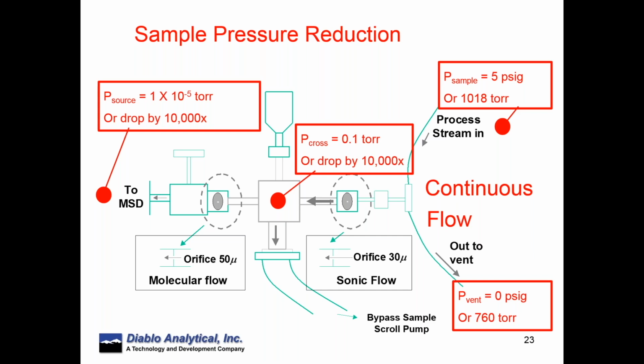And you can see that in the cross on the top, that device is a capacitance manometer that's doing a very accurate measurement of the pressure. And we're going to use that to compensate for pressure changes later. But most of the sample is going to go out the bottom of the cross into the bypass sample scroll pump. That's how we're reducing the pressure, and that's how we reduce the concentration. Finally, a small amount of sample goes across the second orifice, 50 microns in this case, and into the mass spectrometer, which is at maybe 10 to the minus fifth torr. So this is the key design, and the key is that it's very reliable, and it turns out to be matrix independent because of the pressure regimes that we are at in each step of the process.